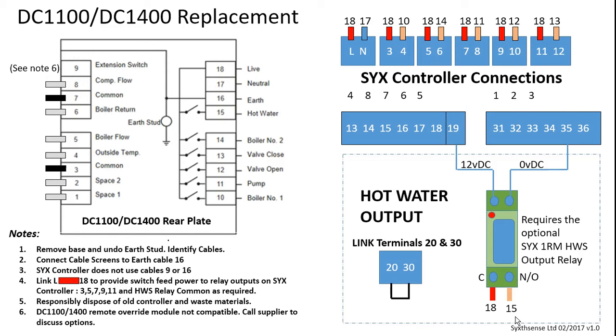Now we can concentrate on the sensor connections. The sensors are a 2-core cable in each particular location. So the outside air sensor will come in on terminal 4, and its common connection will connect into either terminals 3 or 7. So disconnect all of the sensor locations, make sure they're identified, and then we can consider which sensor location goes where. So one side of the sensor connection from the outside air sensor, terminal 4, can connect onto terminal 13. The compensated flow sensor can connect onto terminal 14 if you have it. The boiler return sensor can connect from terminal 6 onto terminal 16 on the SYX controller. The boiler flow sensor can connect onto terminal 17 of the SYX controller.